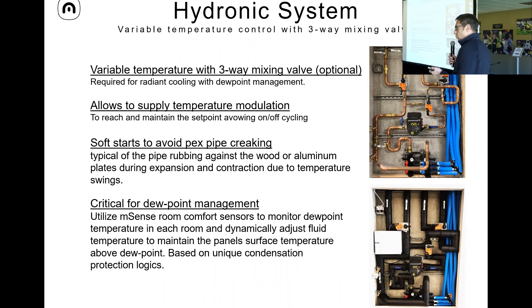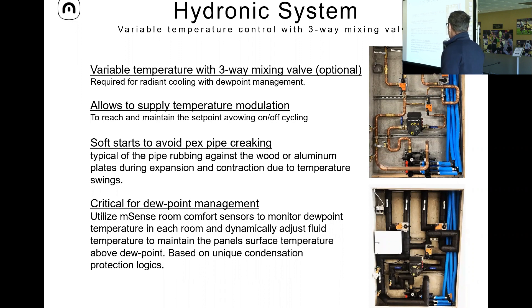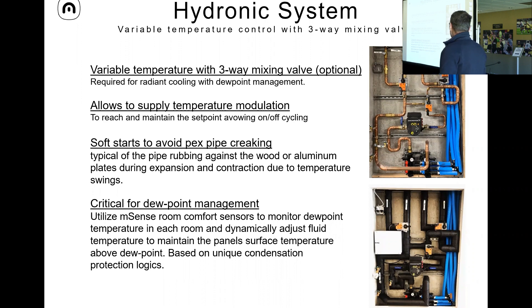It is mandatory for cooling — we really want to have temperature control for critical dew point management. There are also many benefits in heating, like doing a soft start of the system to avoid the creaking of the pipe. We will gently increase the temperature because we have the ability to do so.